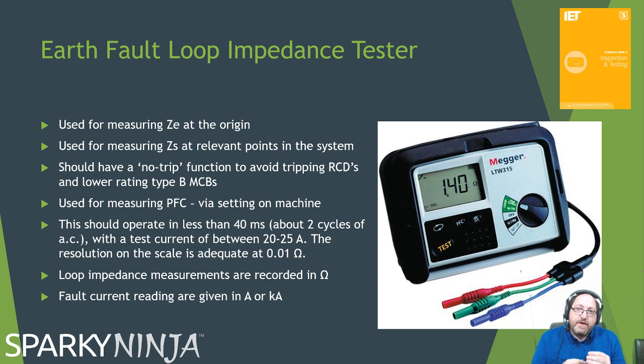In the case of earth fault loop impedances, these are given in the ohms scale. If we switch it though to the kA or the A, that's the amps, that is the fault current scale. So get an understanding that resistances are your ohms and currents are your amps. Get an understanding of the different test readings and test scales, because they could be picked up quite easily in any assessment that you have.